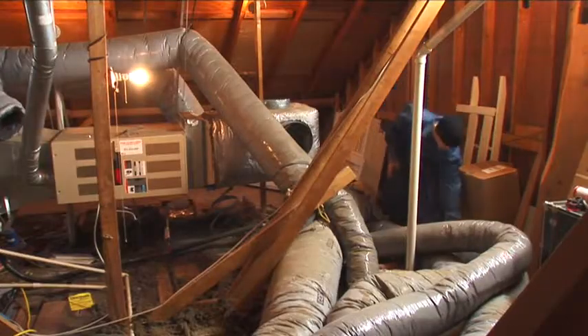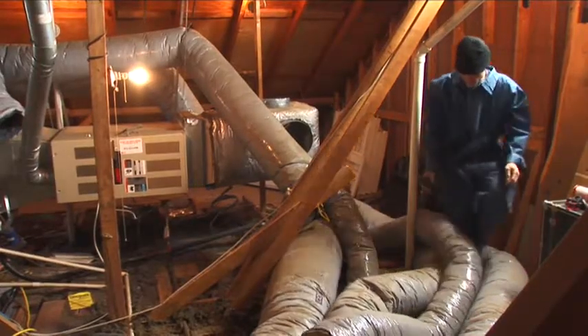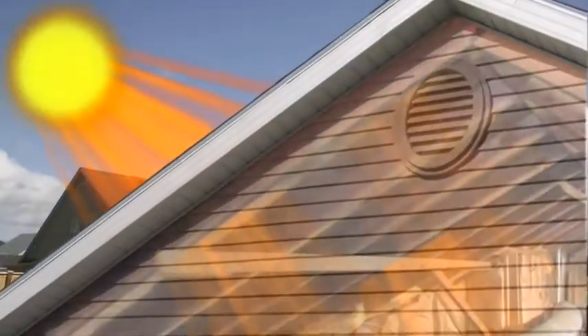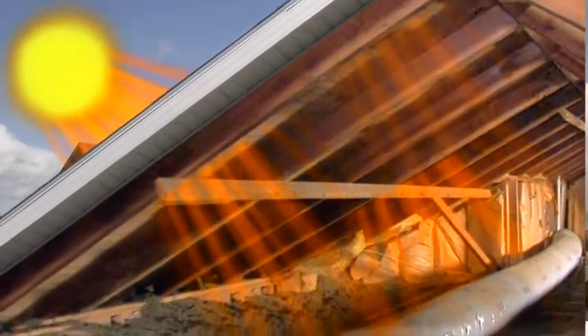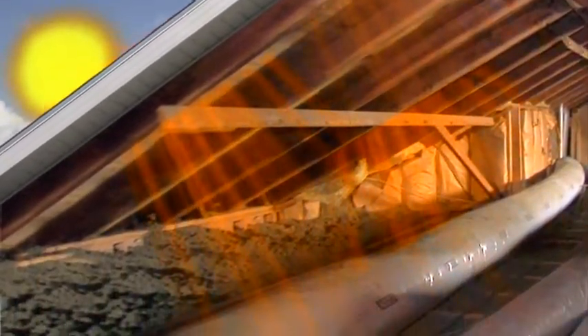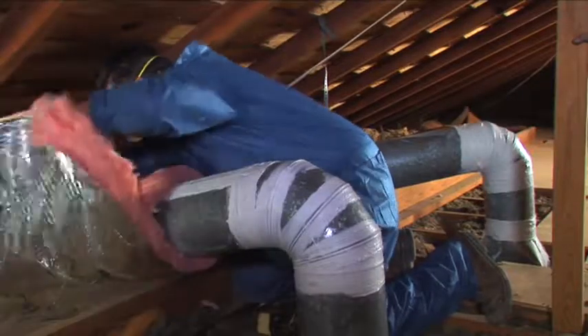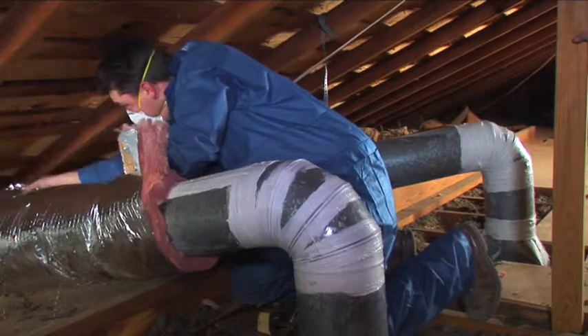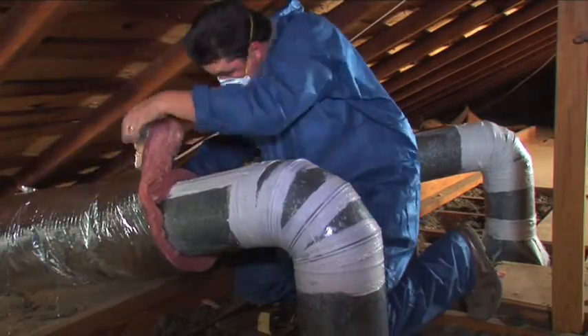Ducts also have other weaknesses. Most only have 1 inch of insulation. Attic air conditioning systems in particular are really affected. Your attic can be very hot in the summertime. 150 degrees is not uncommon. And with only 1 inch of insulation around those ducts, the heat gain can be quite a bit. Many systems absorb so much heat that they lose 1/4 of the cooling energy. So most new building codes now require twice as much insulation around the ducts.